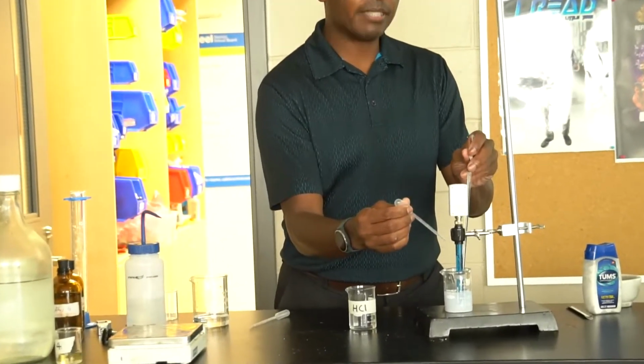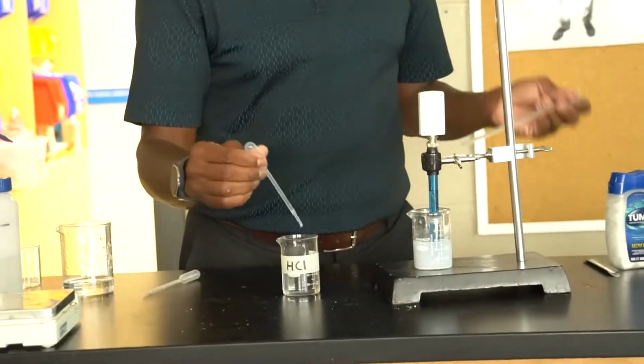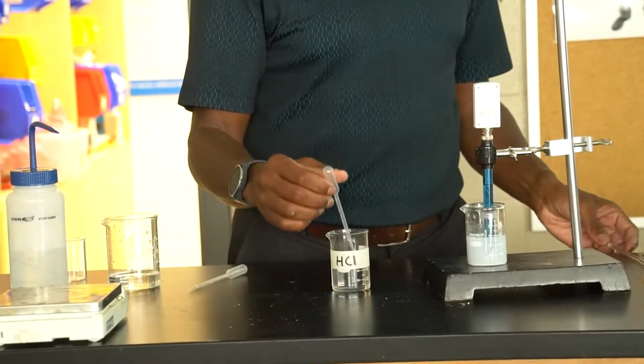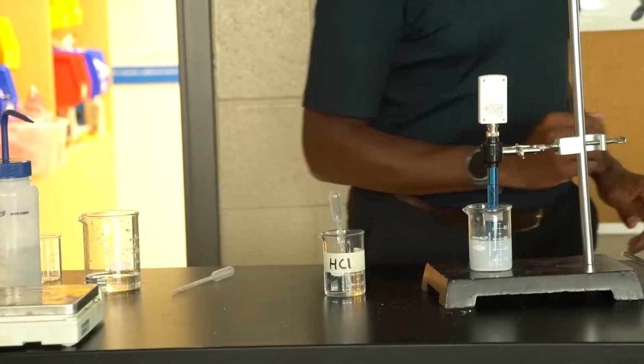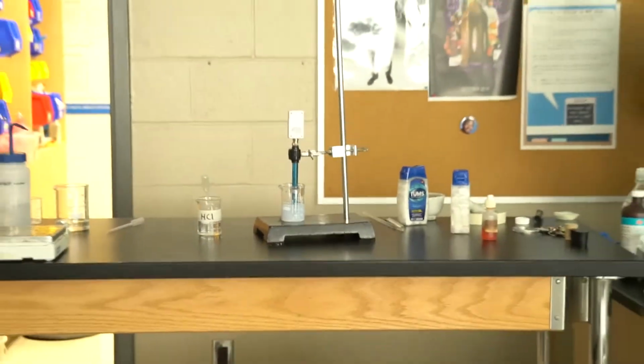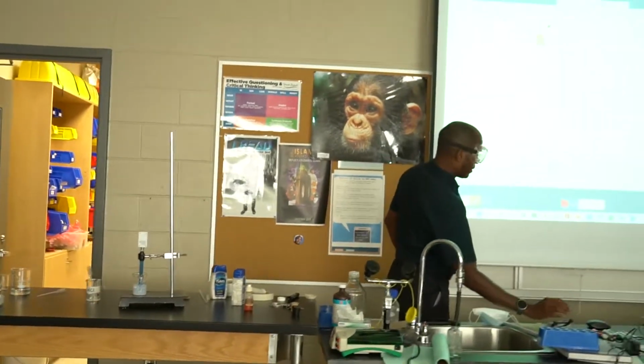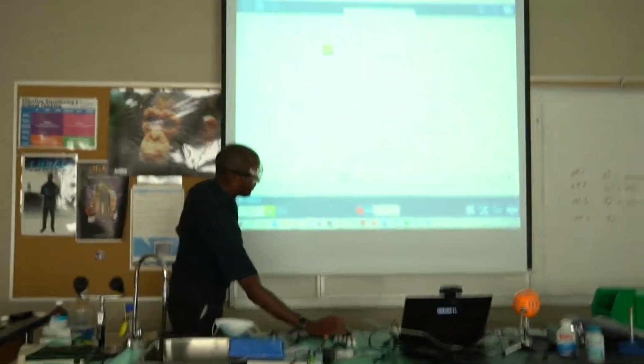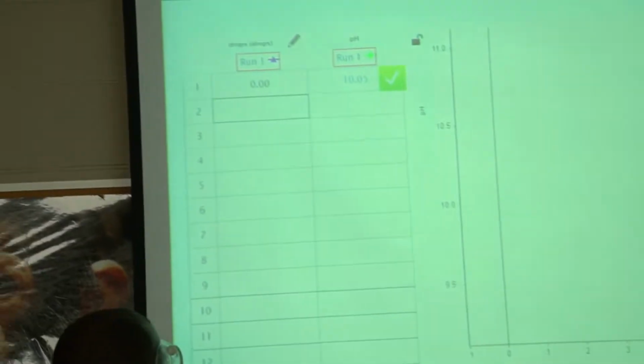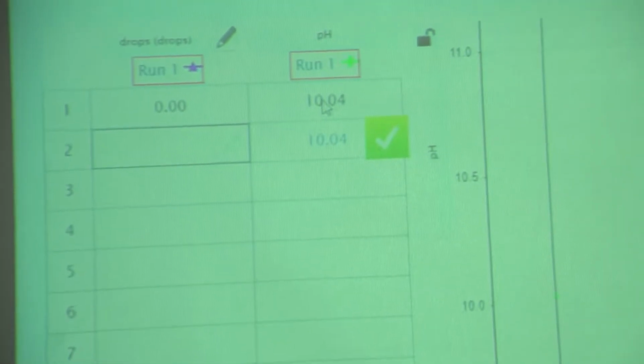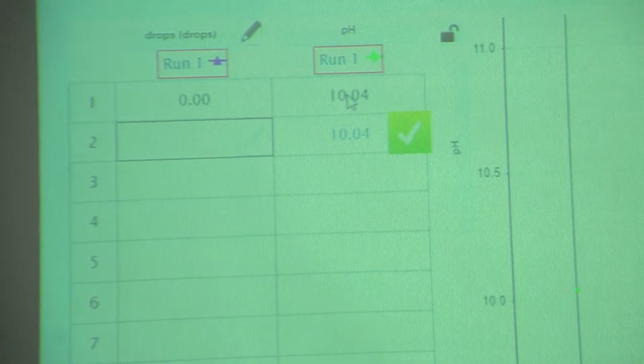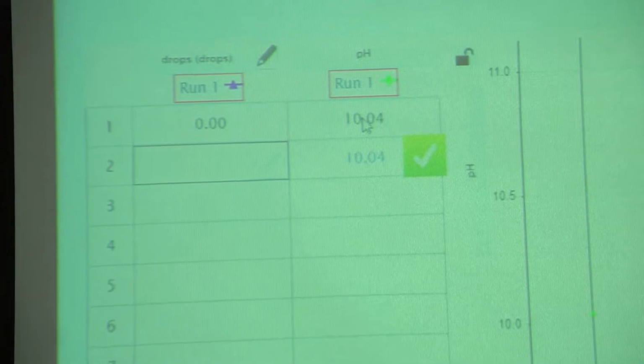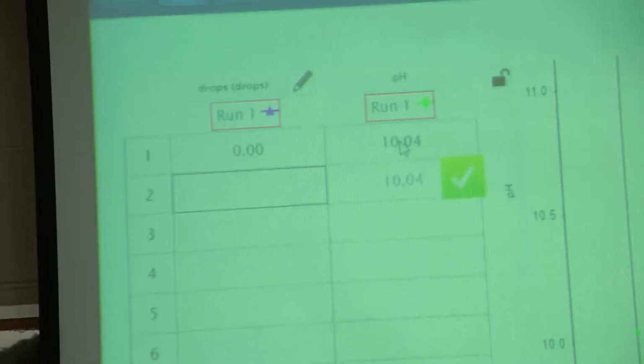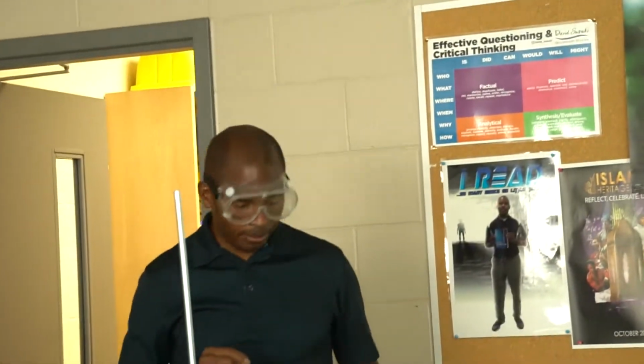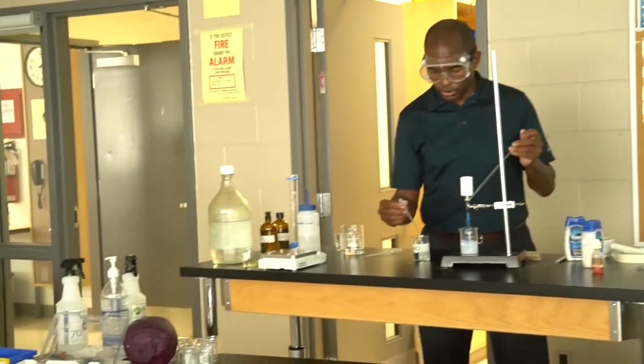When I get to a pH of 2, I want to stop. Now the way I have the screen set up, you cannot see your value currently. So since I started at 0, I'm going to click on this check mark, and it's now locked in my starting value of 10. So my starting value of 10-ish is 0. Now as I add my drops, you're going to see that 10 is going to drop to something that's more neutral, and then acidic.